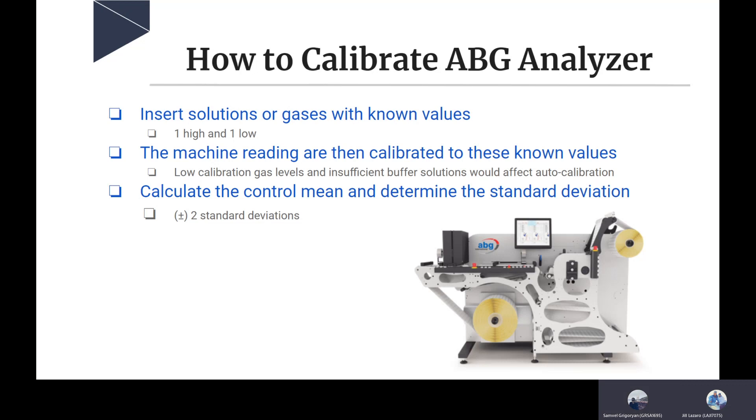What we're really looking for is that our calibrations are within two standard deviations. When we calibrate them, we want to make sure that our control mean is determined properly and that we are within the measurements that are allowed for our machine to be working properly.